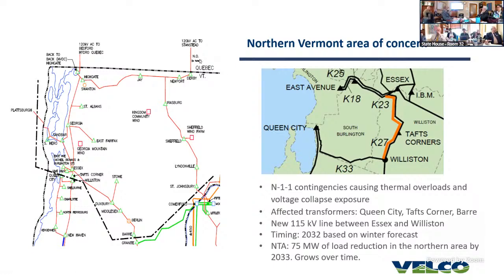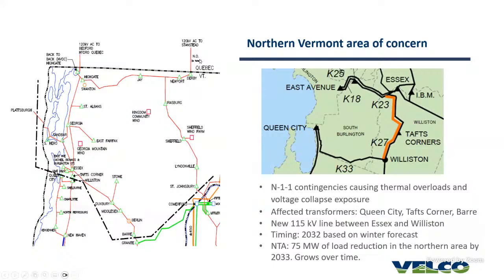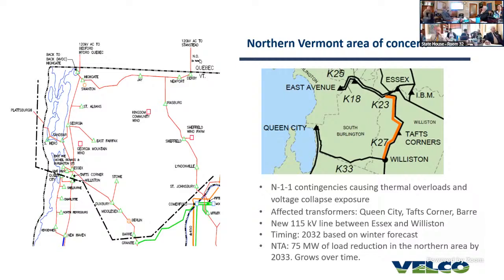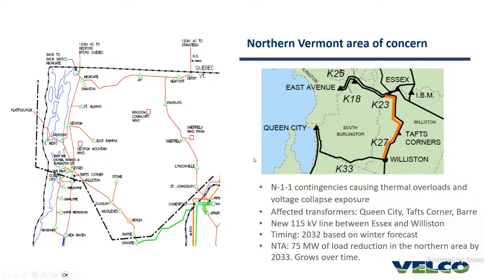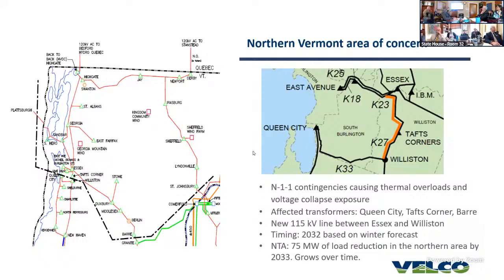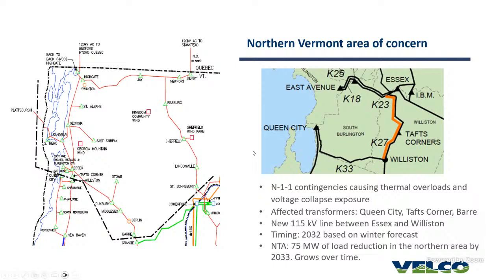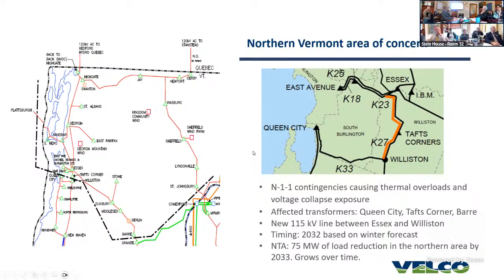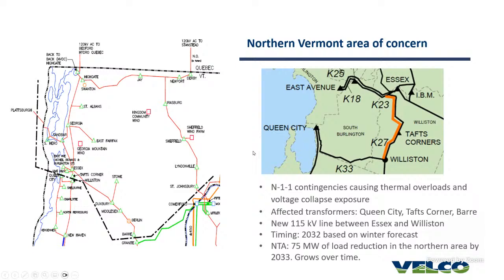So the transmission approach would be to add a new line between Essex and Williston, shown there in orange. That creates redundancy so that the loss of the existing line between Williston and Taft's Corner won't create this problem. That would be one solution. In terms of timing, we looked into when the problem happens, and 2032 winter is when that line needs to be in place.